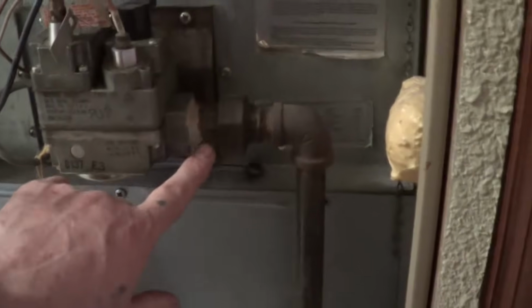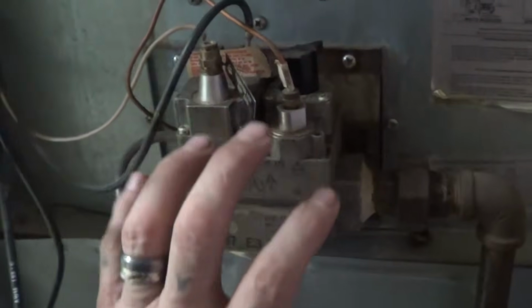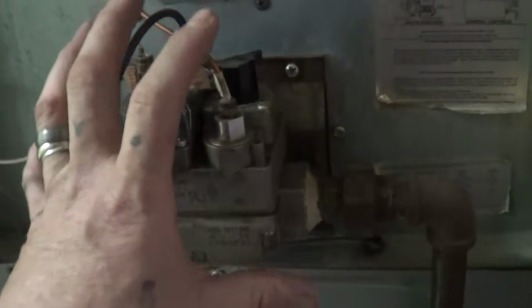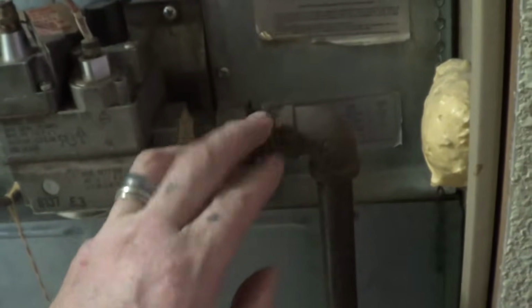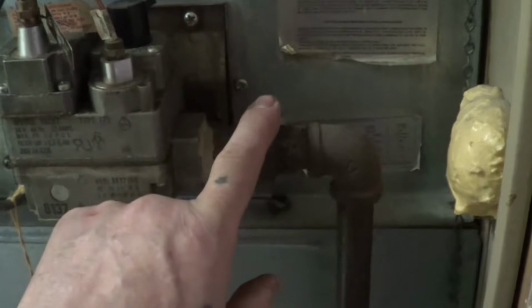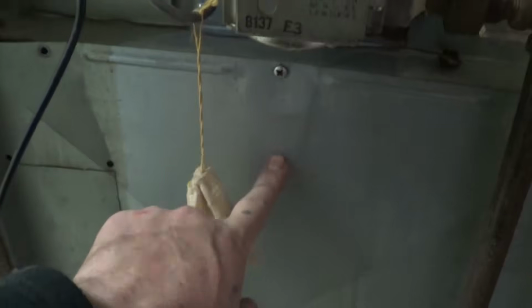The best thing you can do if you can't get inside here - for instance, this one has a hard pipe and a valve. We'd want to pull the valve out and look inside to see the heat exchanger, but we can't do that, or rather, I just don't want to go through disconnecting all this, potentially causing a gas leak when we try to put it back together, having to shut it off, relighting the pilot, and all those kinds of things. So what we can do is pull this panel off right here.